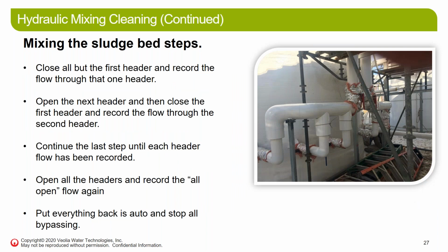After you have the system in the correct flow with everything open and the least resistance, you're going to close all but the first header and record the flow rate on your flow meter for that one header. Then open the second header slowly. Again, do this all slowly because you're putting more flow through the system. You don't want to hydraulically shock anything. Record, then open the second header and close the first header, so you again have flow going through one header. Record that flow. Continue that step until each header flow has been recorded. Then open all the headers again and record the all-open flow again.